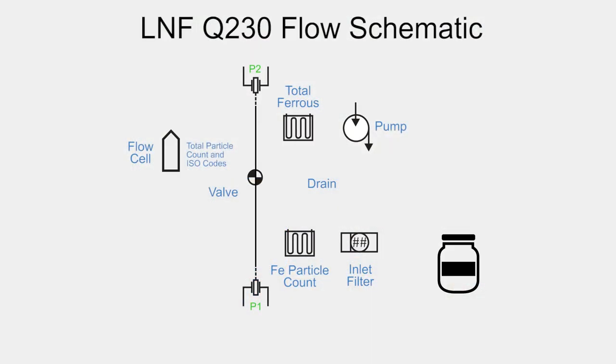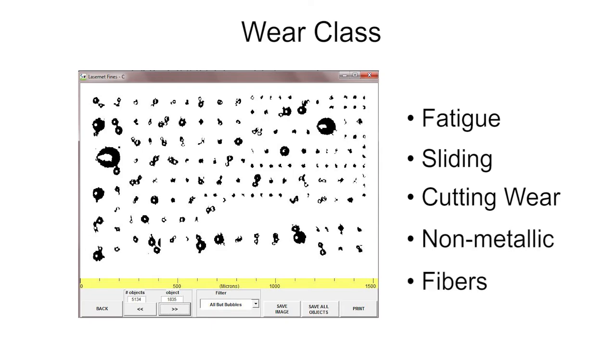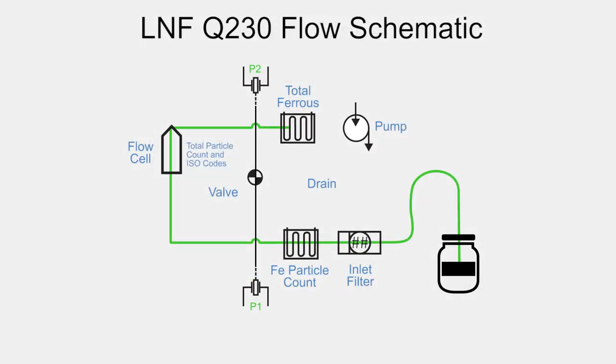The schematic here shows the flow path of the LNF. The sample is drawn up through the tube through a 100 micron filter that removes large particulates and enters the first portion of the ferrous monitor, a high-sensitivity magnetometer which measures the ferrous particle count. The sample then enters the LNF flow cell, which uses laser light and a CCD detector to image each individual particle. This provides particle count in ISO codes and also characterizes all particles greater than 25 microns into a wear class, either fatigue, sliding or cutting wear, non-metallic or fibers, based on the shape of the particles. Finally, the sample enters the second magnetometer, which measures total ferrous content in PPM.